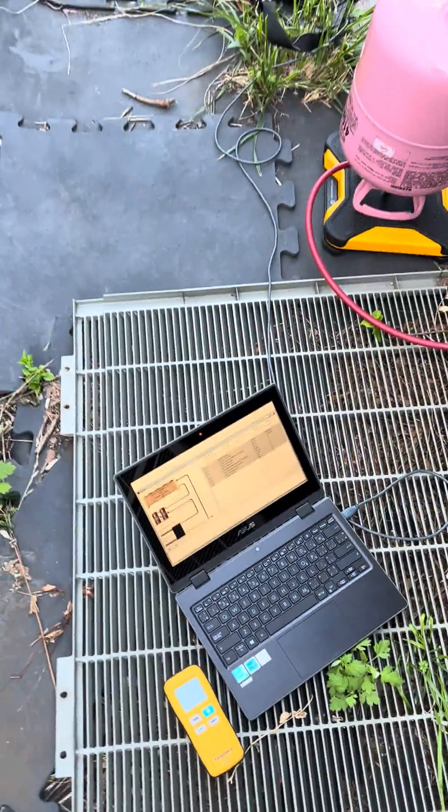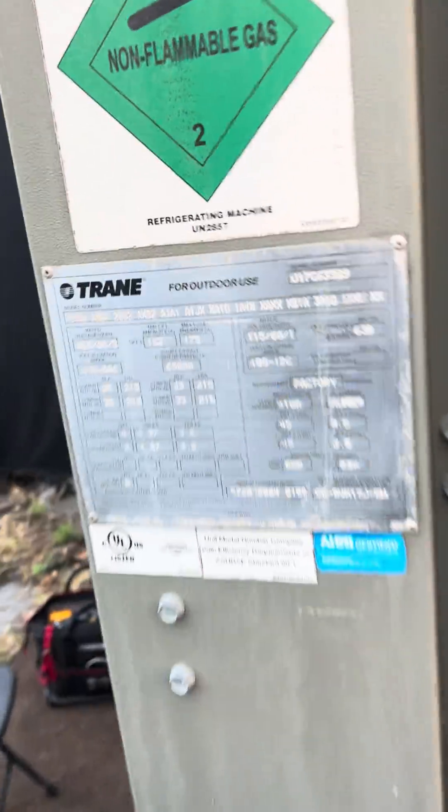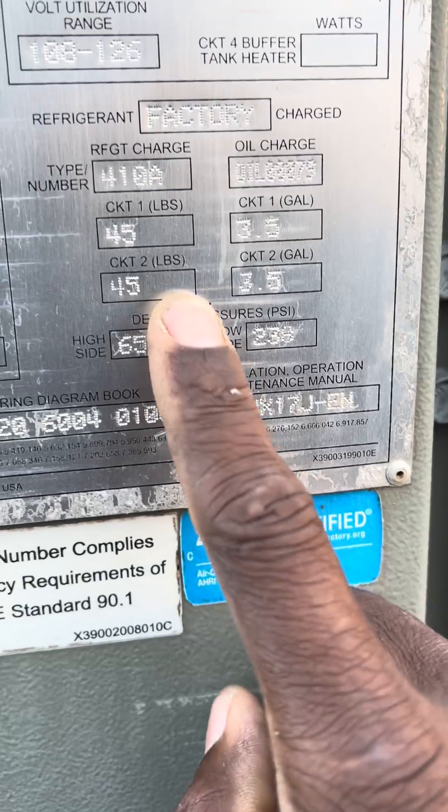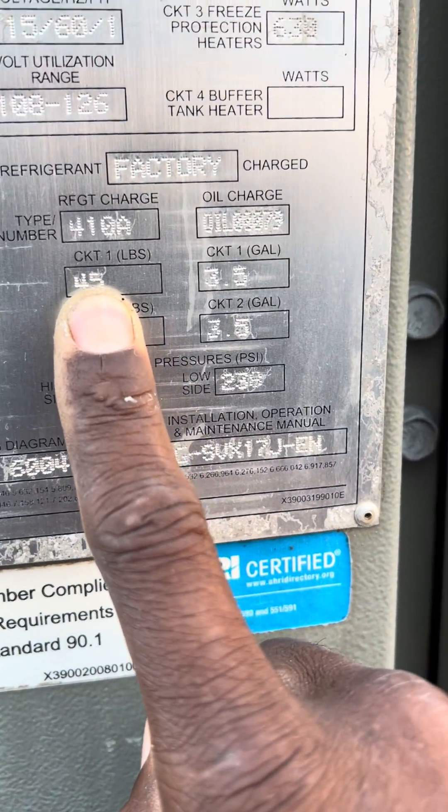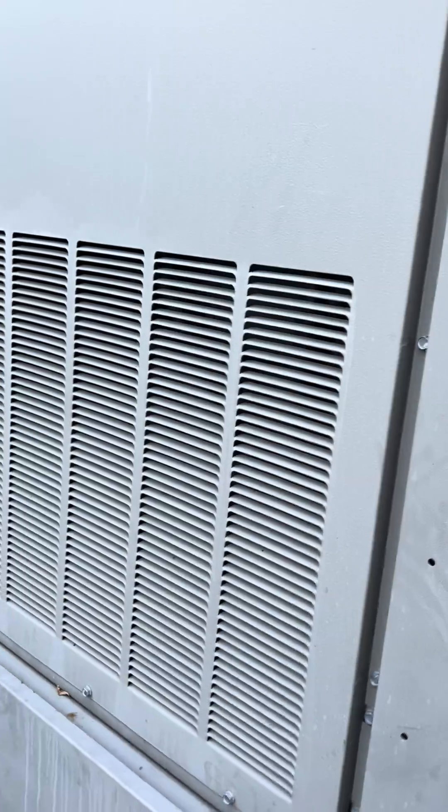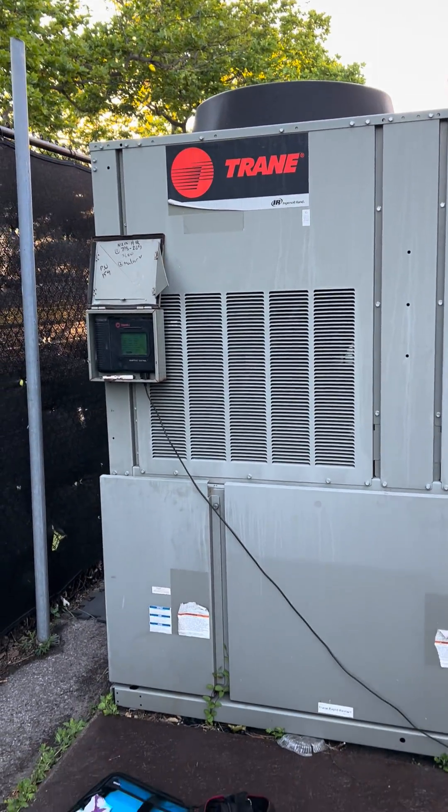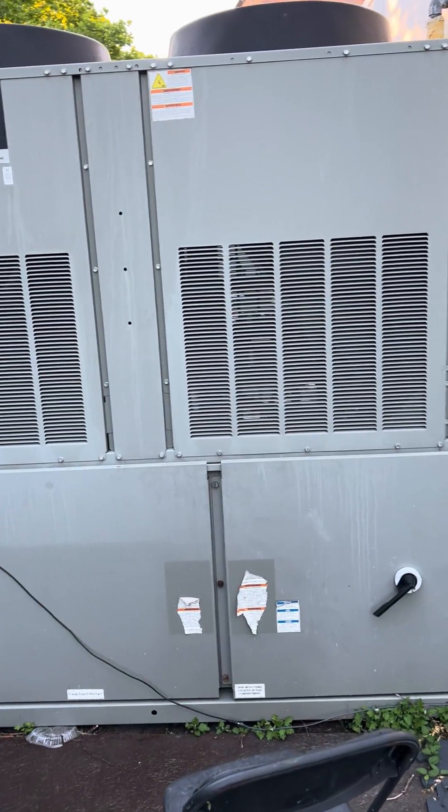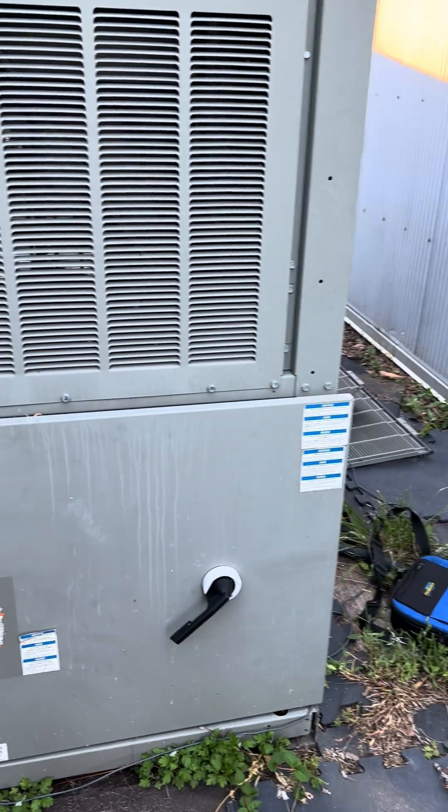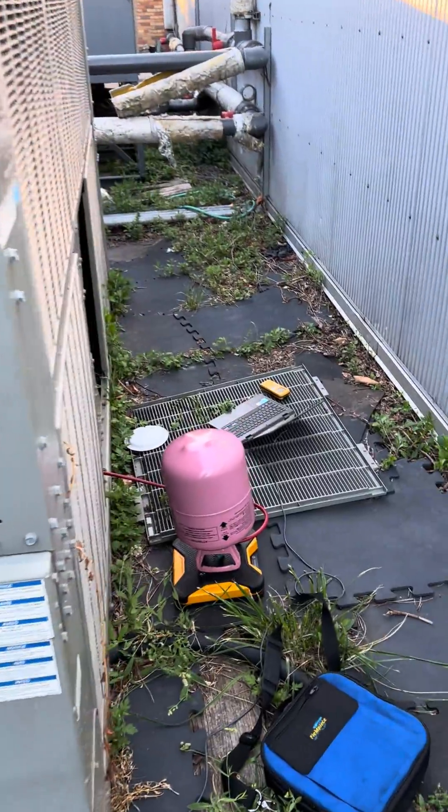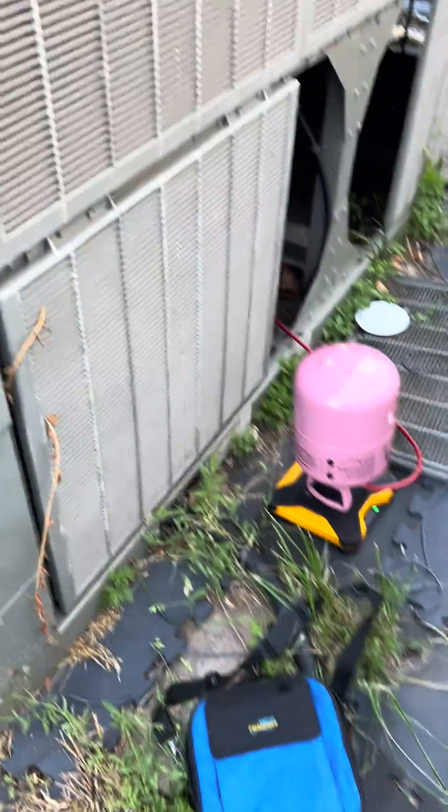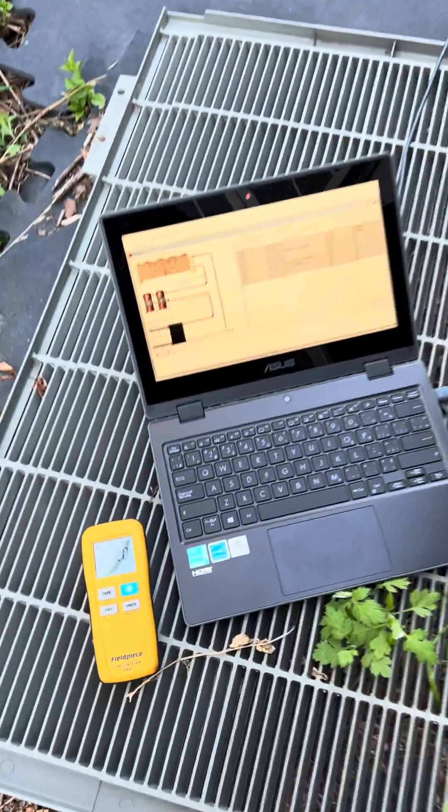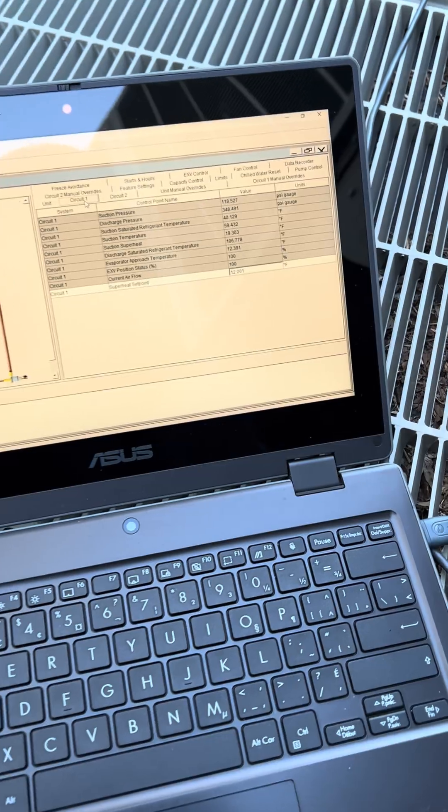The total charge on this thing, let's see how many pounds it takes. 45, that's 45 pounds per circuit. This is the chiller if you're wondering what it looks like. I think we may have a leak, a small leak or something like that because the pressures indicate that. So the alarm is merited unless I got a faulty suction and discharge pressure transducer which I doubt. I think we got a slight leak on this thing.